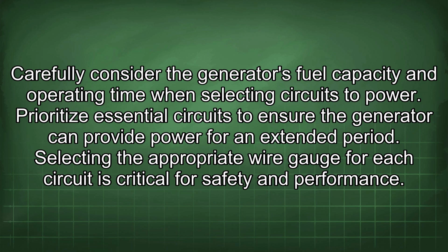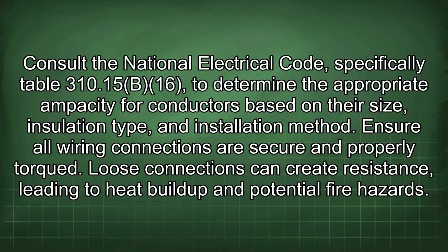Selecting the appropriate wire gauge for each circuit is critical for safety and performance. Consult the National Electrical Code, specifically Table 310.15(B)(16), to determine the appropriate ampacity for conductors based on their size, insulation type, and installation method. Ensure all wiring connections are secure and properly torqued. Loose connections can create resistance, leading to heat buildup and potential fire hazards.